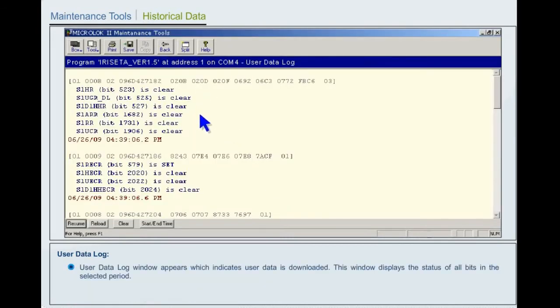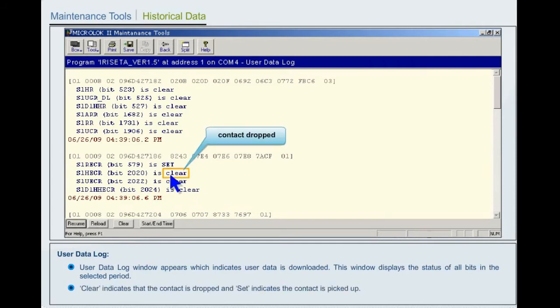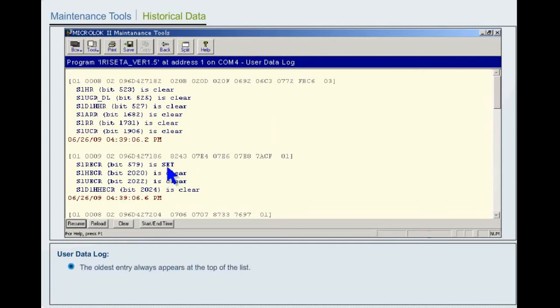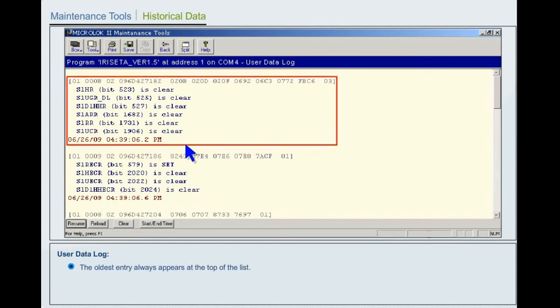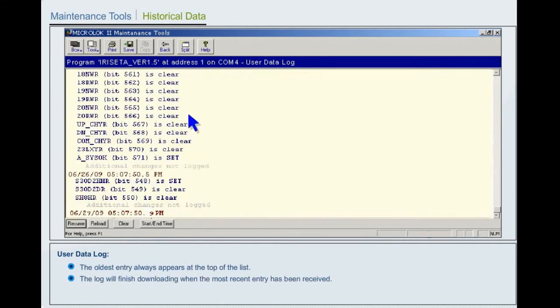Step 3. User Data Log window appears, which indicates user data is downloaded. This window displays the status of all bits in the selected period. Clear indicates that the contact is dropped and set indicates the contact is picked up. The oldest entry always appears at the top of the list. The log will finish downloading when the most recent entry has been received.